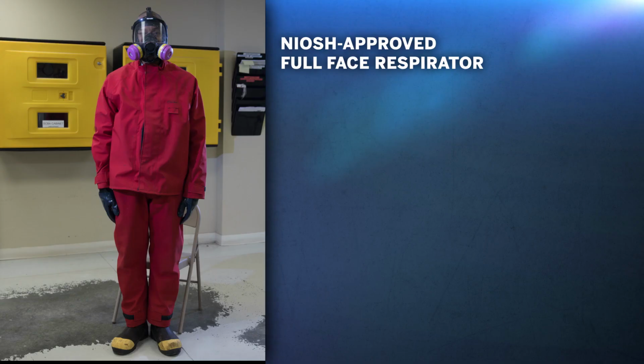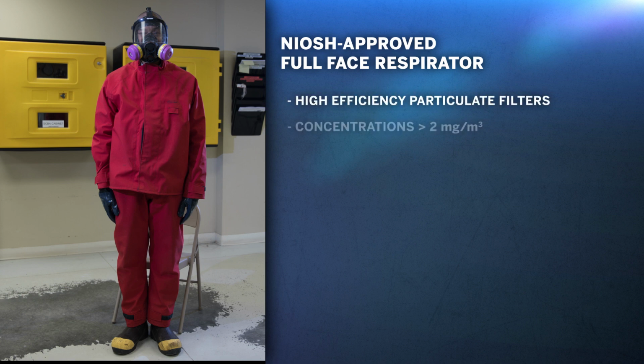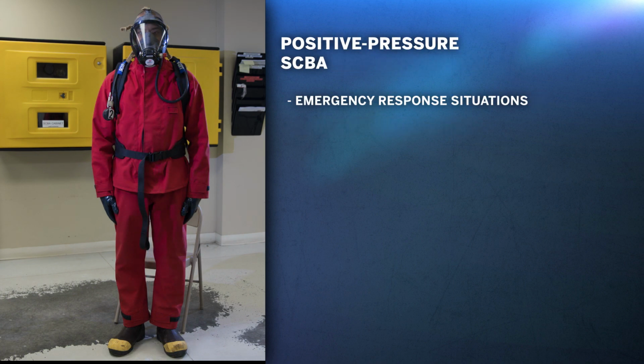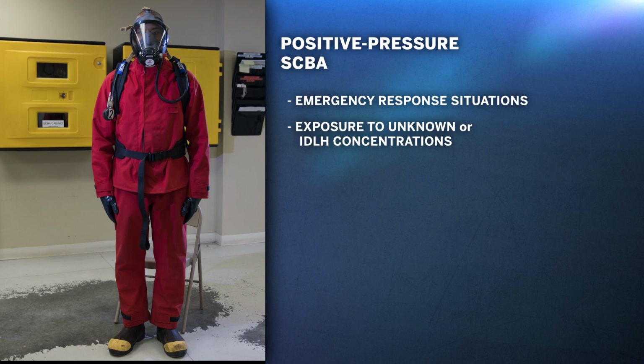A NIOSH-approved full-face respirator with high-efficiency particulate filters should be worn when dust or mist concentrations exceed the permissible exposure limit of 2 mg/m3. A positive pressure self-contained breathing apparatus, or SCBA, is recommended in emergency response situations that involve exposure to unknown or immediately dangerous to life and health (IDLH) concentrations of caustic.